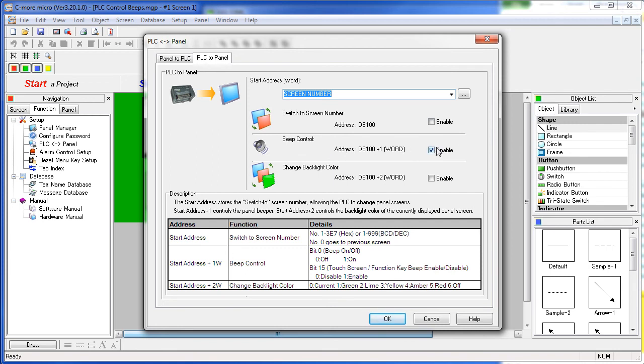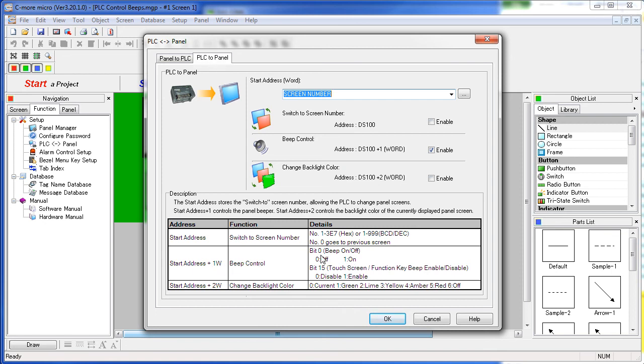With this enabled, when the PLC writes to the screen number plus 1, the C-more Micro will be watching that and will react accordingly. Note that there is a handy reference down here that tells you that at that address, if the PLC writes a 1 to bit 0, it will turn the beeps on. If it writes a 0, it will turn the beeps off.